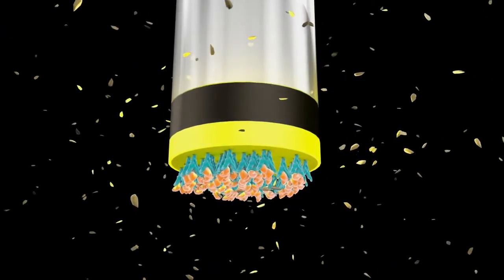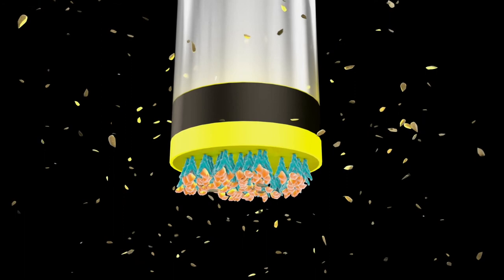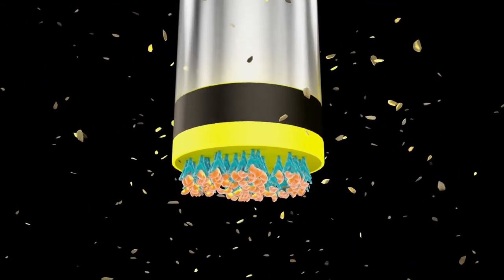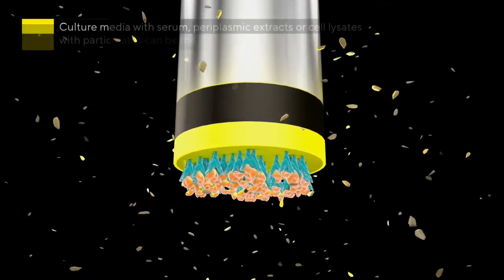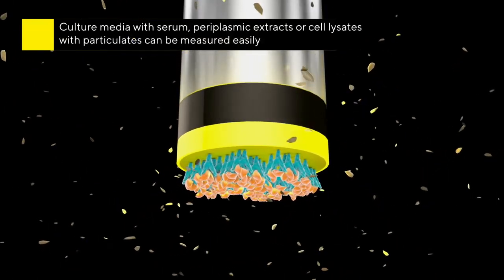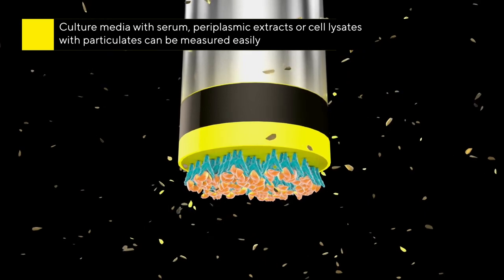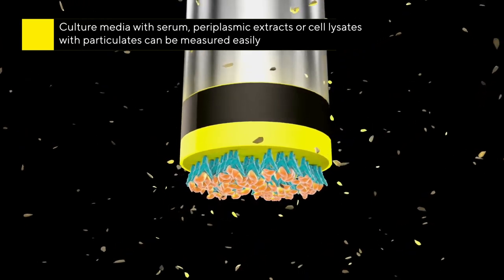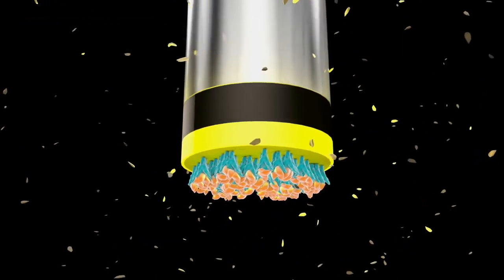A unique characteristic of BLI is that only analyte binding or dissociation can shift the interference pattern and generate a response profile. Unbound molecules, changes in the refractive index or pH, or other matrix effects do not affect results, making this technology well suited to measurements in crude samples.